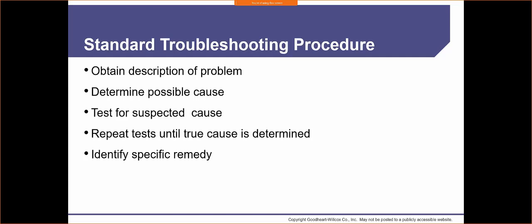And we'll talk about sequence of operation a little bit. You're going to test for a suspected cause. You're going to repeat the test until a true cause is determined, and then identify a specific remedy. Okay? So if we go down there and we realize that our inducer is bad, we're going to try to test it, or we're going to see that our inducer is making a noise. Great. We've found that that problem is ongoing. It may repeat itself for us. It may not. Sometimes gremlins disappear when us technicians show up on site, and it's hard for us to repeat that process. So we have to be aware of that, but we're going to do the best we can.